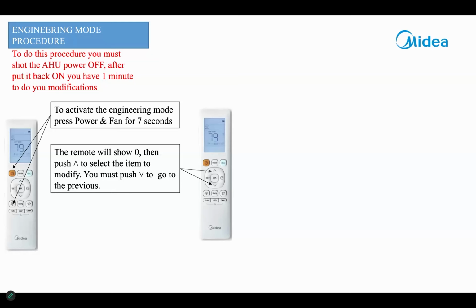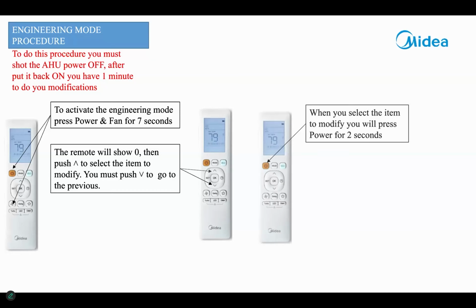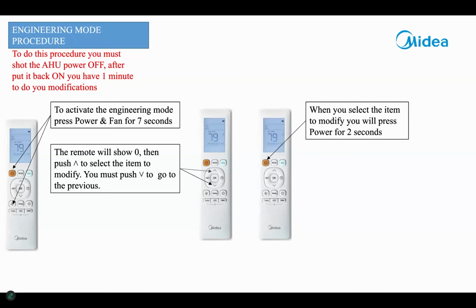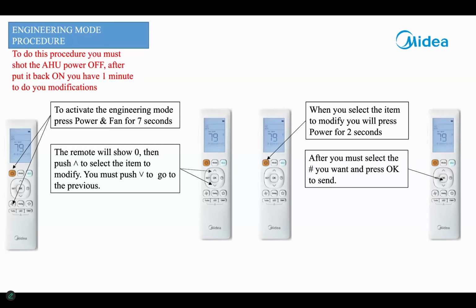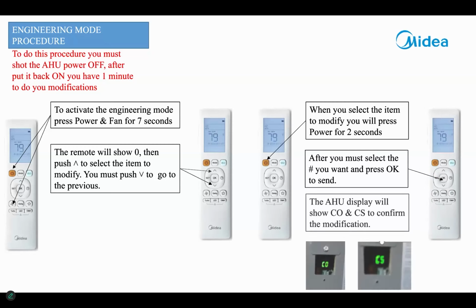Then you press and hold the power button for 2 seconds. This is going to show CH for channel number 2, and it's going to show the actual data that it's set at. Use the up or down buttons to change the data. Then you're going to select OK. OK sends that parameter to the board. It should respond with COCS, meaning command successful.